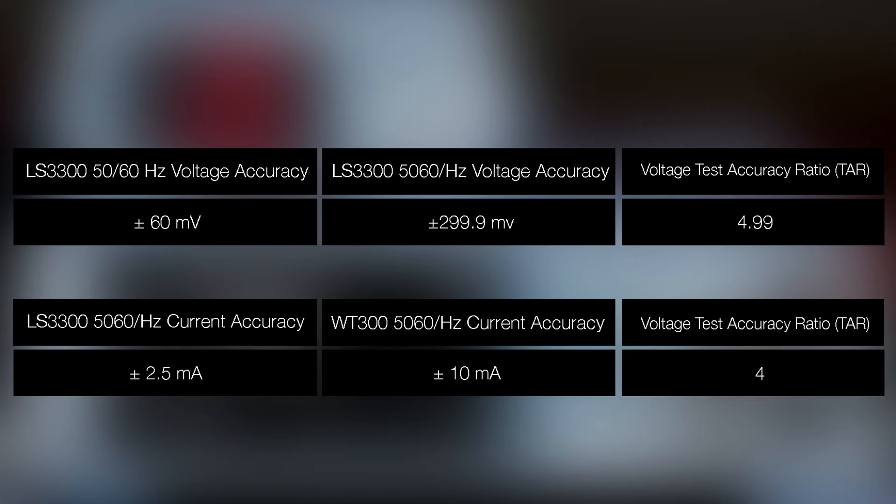As well for the LS3300 at 60 Hertz, the current accuracy at this range and setting is plus minus 2.5 milliamps with the WT300 accuracy being plus minus 10 milliamps. This provides a TAR for current equaling 4, passing the minimum required ratio.